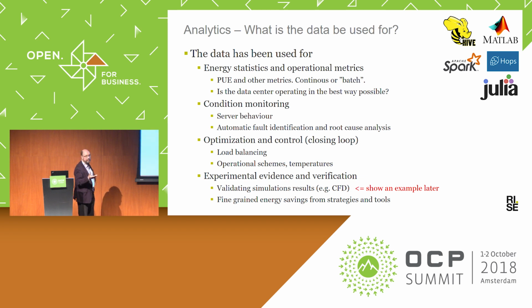There are other metrics we might want to look at. PUE is not an efficiency metric, so if we wanted to look at IT efficiency as part of data center efficiency, we may look at some of the proxies that have come out of the Green Grid. We could try that because we're monitoring data traffic and what the IT systems are doing, so we've got information from the whole stack, as it were. And of course, there's also continuous monitoring for fault identification and root cause analysis.